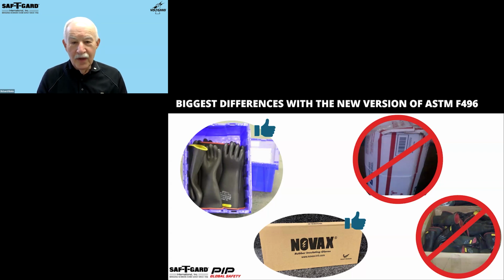The ASTM standard on field care inspection and storage also states that rubber insulating gloves shall be stored in their natural shape. Rubber insulating gloves shall not be stored folded, creased, inside out, compressed, or in any manner that will cause stretching or compression. Don't just throw them in a box. After all, these are the products that can save lives. And by the way, don't try to fix them with electrical tape. I've seen it, I don't believe it, but it happens.